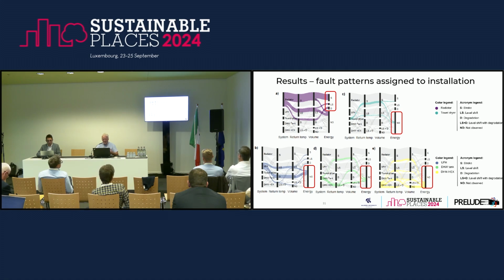This picture shows the consequences. We looked at different types of technologies — radiators, underfloor heating, towel heaters, and so on — and show the return temperature, volume, and energy flow. It seems that faults in the radiator systems actually have an impact on energy use, shown in picture A in the top left corner, while other faults do not reflect much in energy use. These are more short-term faults which don't influence overall energy use, but they do increase return temperature and volume flow. This can be critical for the capacity of the system if the volume flow increases very much.